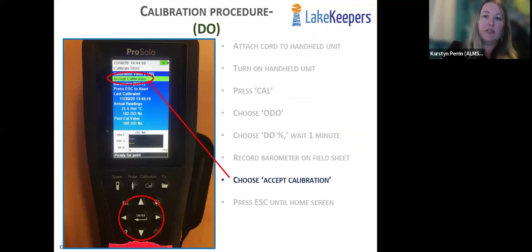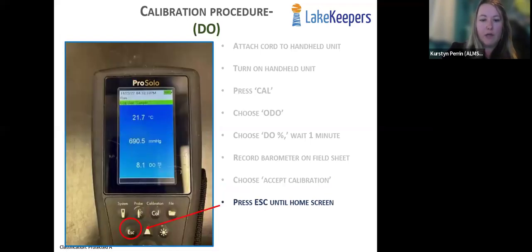Once those lines look good, then you can choose to accept the calibration, and you should receive a calibration successful message at the bottom. If you don't, and it says that it's a questionable calibration, don't accept. Go back through, redo the process, make sure everything's dry, no cracks or anything, and give us a call if you try it again and it's not working. Once it goes through, then you can just press escape and it'll bring you back to the home screen.